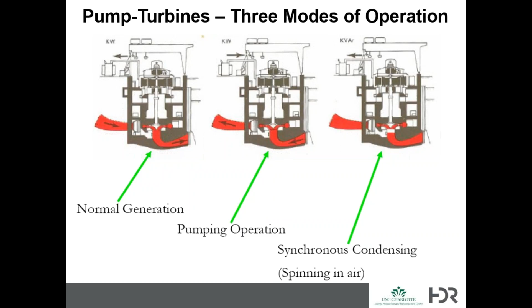And you go through commissioning and testing. If you stand on top of the head cover and you're trying to pump, the turbine, at 500 tons of mass, is rotating in the pump direction. If you miss the timing to open the gates to let the water go uphill, the water comes through in the generate direction. The water is screaming in under 1,200 feet of head, going in the opposite direction to the way the pump impeller is rotating, and you'll want to bring a change of clothes, because you just think the world is coming to an end. And you're 500 feet in the mountain underground, and it's black.